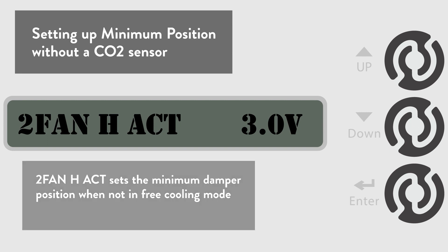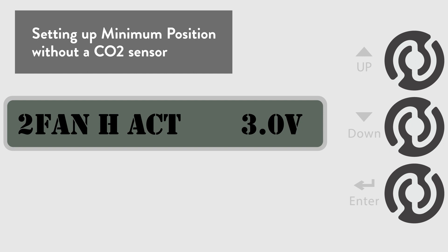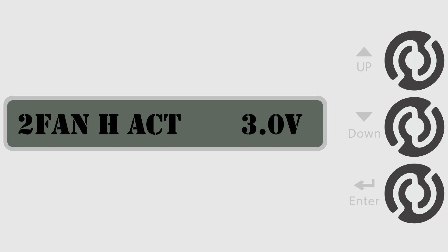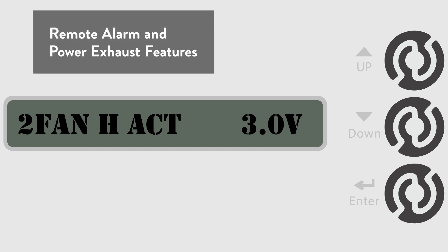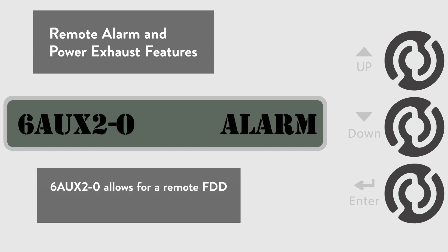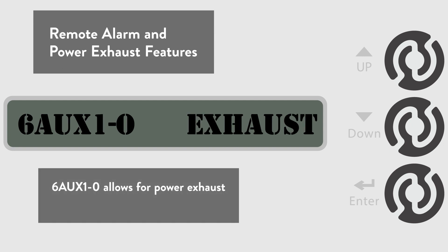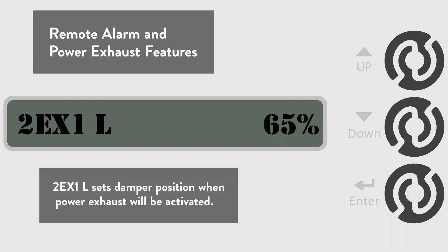The last two items we are going to discuss are for informational purposes. We are going to look at the settings for power exhaust activation and alarms for fault detection. Even if you do not use these features, you can leave the settings at the default. Scroll down to the 6 AUX2-0 menu. The default is set to alarm to allow a signal to be sent to a remote light or thermostat signifying that a fault has been detected on the economizer. The remote alarm feature is required by many building codes including California's Title 24. Our last example will be the 6 AUX1-0 menu. The default is set for exhaust for use with a power exhaust. To change the activation setpoint, go to the 2-EX1-L menu, where the default is set for the power exhaust to kick on when the outside air damper is open to 65%. But for this example, we are going to change it to 75%.